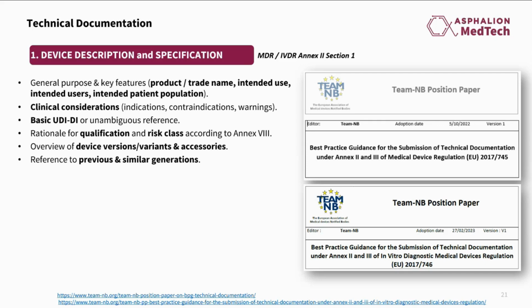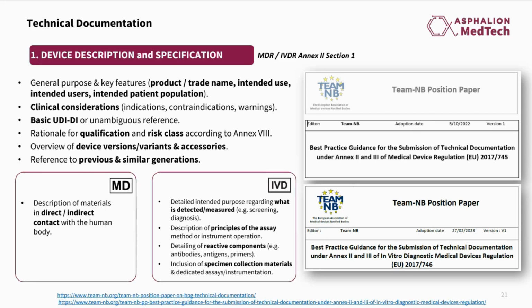Basically, you have to have an area describing the technology and also its specifications. Here it includes the intended use, intended user, intended patient population, the risk classification of your device, and the different versions or variants of your product. Specifically for medical devices, you need to talk as well about how the different parts of the device are in contact, direct or indirect, with the human body. And in the case of the IVDs, you need to focus on the principles of the assays to detect the specific analytes.